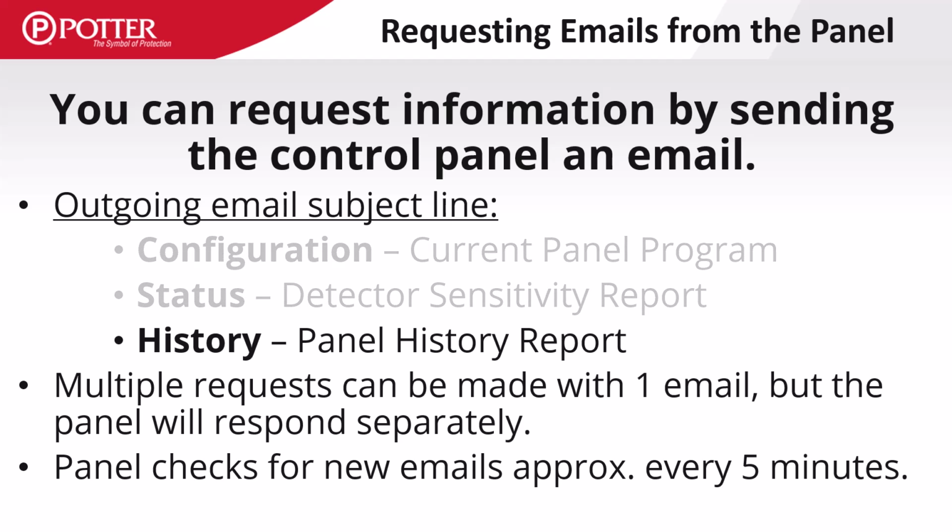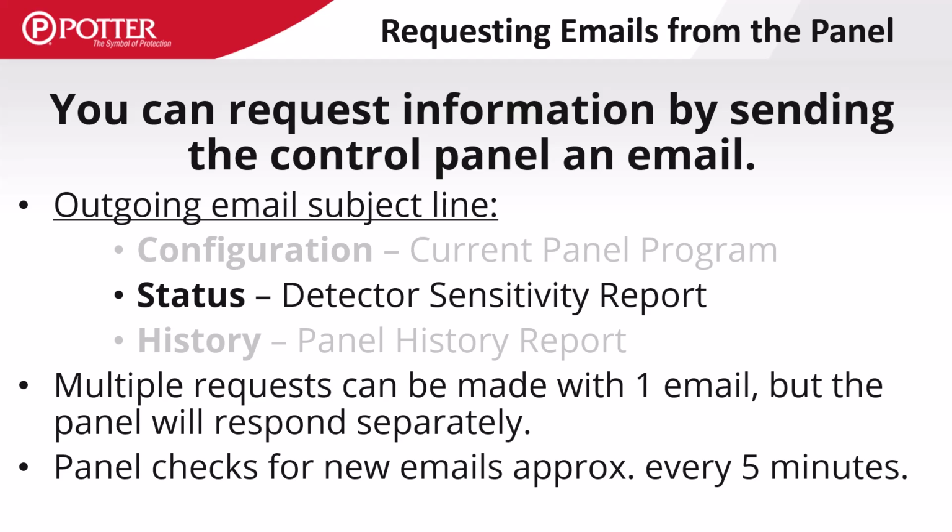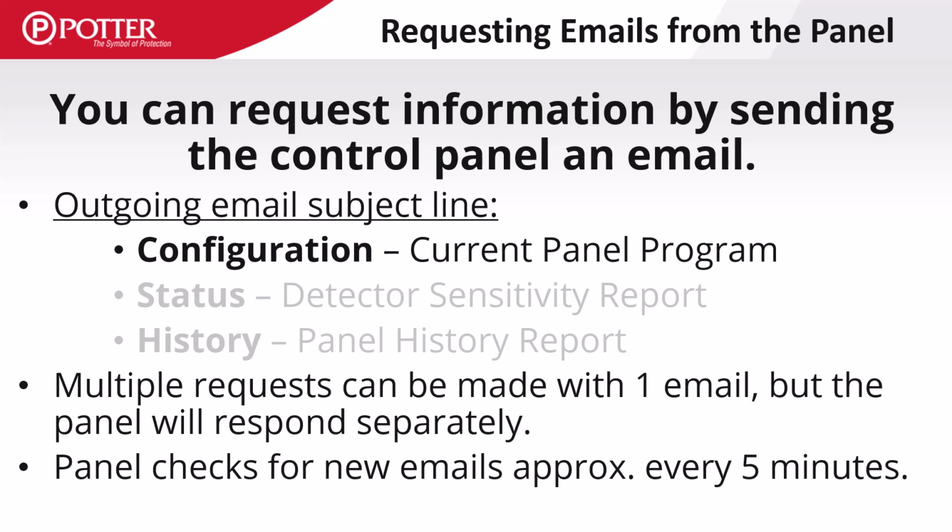Entering history in the subject line will cause the panel to reply with a history report attached. Entering status will result in the panel sending the detector sensitivity report. And the keyword configuration will cause the panel to send a copy of the panel's current program file.